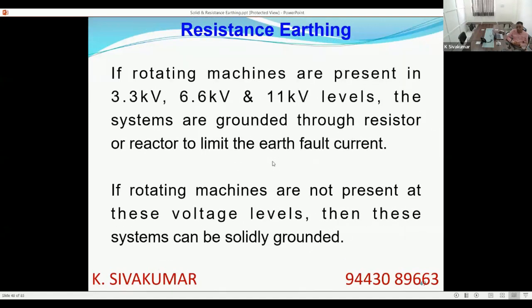So if rotating machines are present in 3.3 kV, 6.6 kV, 11 kV, the systems are grounded through reactor or resistor to limit the earth fault current. If rotating machines are not present in this voltage level, these systems can be solidly grounded. Now a big question comes. If you want to protect the rotating machine, if you see the population of rotating machines, the population of rotating machines is very high in low voltage only. That is below 1000 volt, 415 volt system.